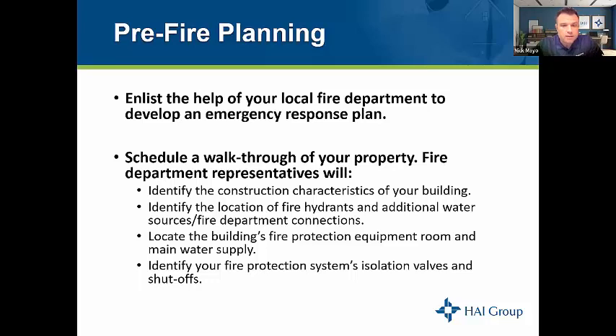Locating the building's fire protection equipment room is important, especially in the fire service, because firefighters want to know where that room is so they can know where the main water shutoffs for the building are, if they need to isolate a valve. Especially on the outside of that building, that's where the fire department connection will be. So that's where they'll connect their hose on the exterior of the building to feed either the sprinkler system, standpipe system, and along with that, the building's fire pump.